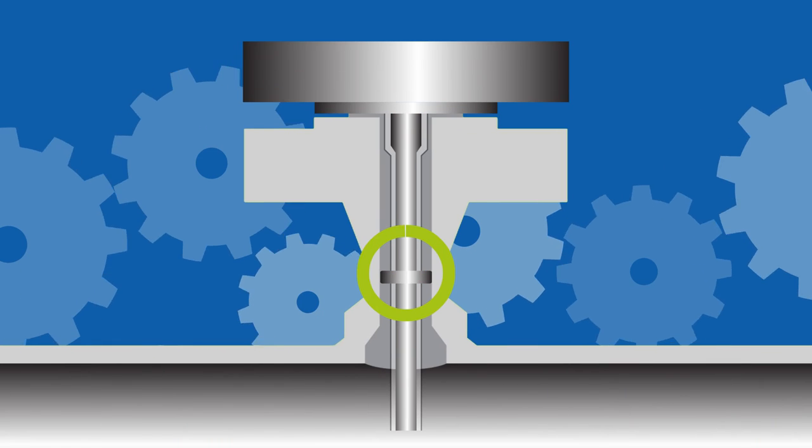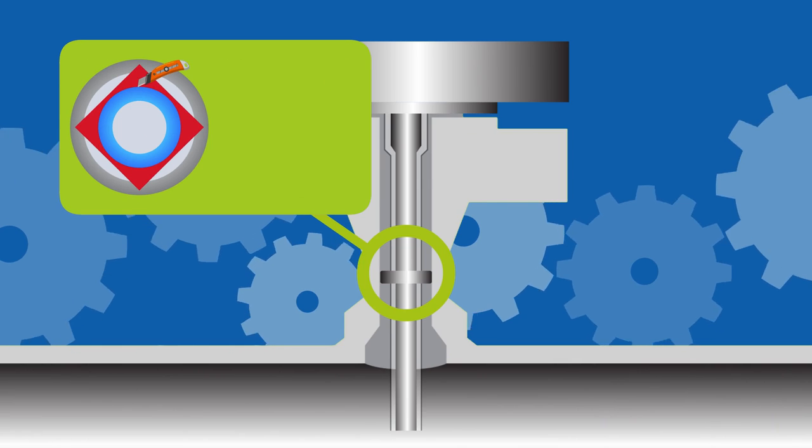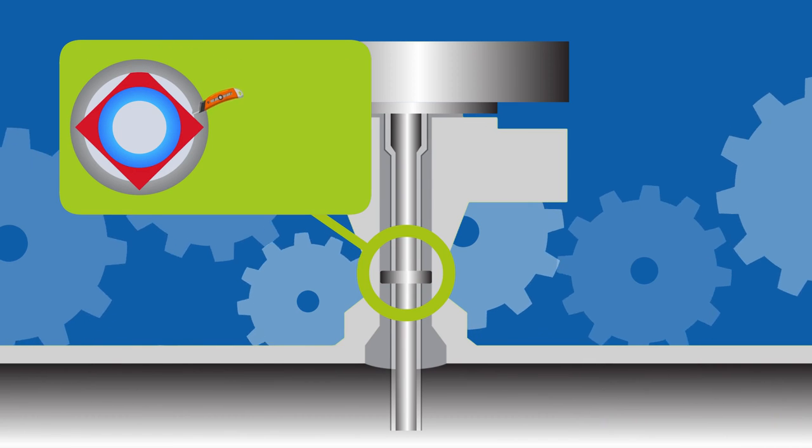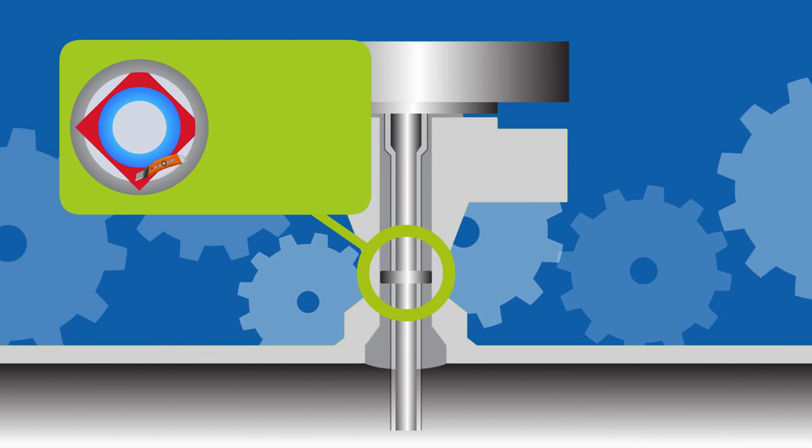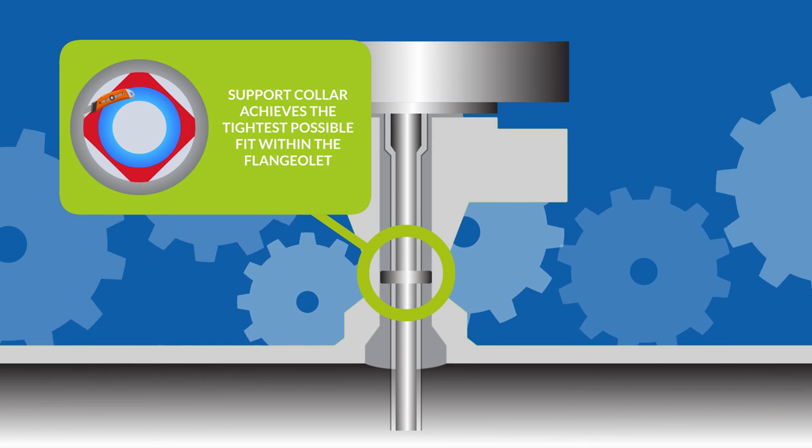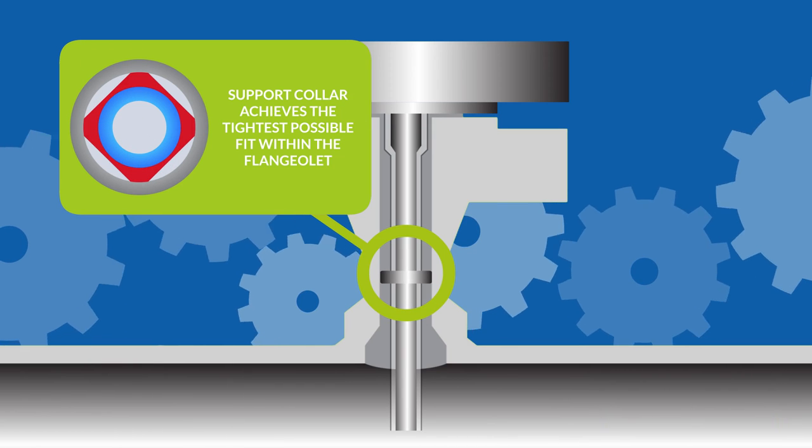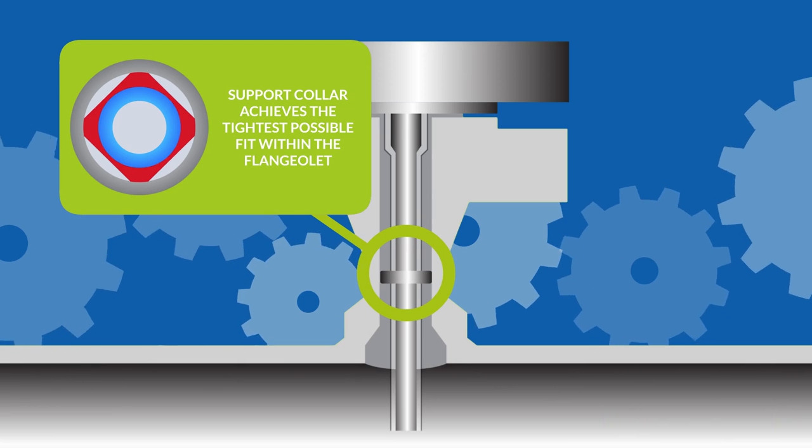On site, the installer will place the injection or sampling DBB valve on top of the flangeolet and evenly cut off some material from the four-point collar so that the collar achieves the tightest possible fit within the flangeolet.